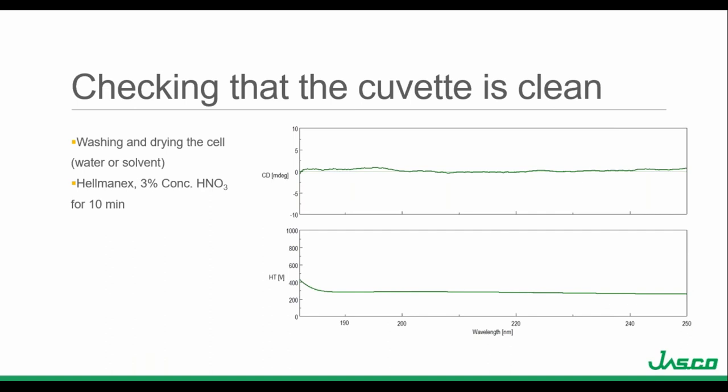JASCO also offers two microsampling accessories: a microsampling disk for spectral scans using only 2 or 10 microliters depending on path length, and a capillary cell for thermal stability studies holding about 10 microliters with a 0.5 mm path length. While most quartz rectangular cuvettes have little to no birefringence and flat baselines, baseline measurements should be performed to ensure no optical artifacts. Cell baseline measurements can also confirm cleanliness. Cuvettes can be cleaned by washing with water, solvent, or detergents such as Hellmanex — you can sonicate in Hellmanex, soak, or if needed, rinse with concentrated nitric acid.